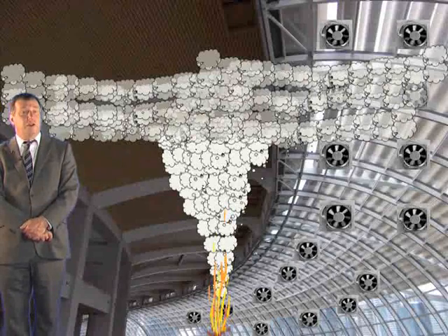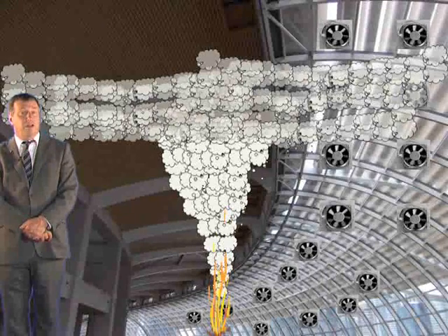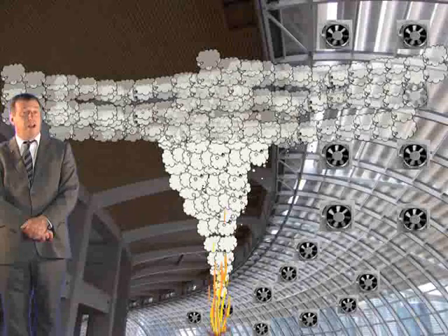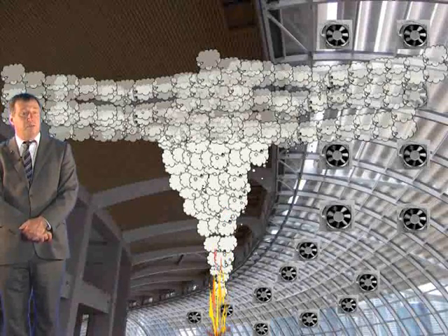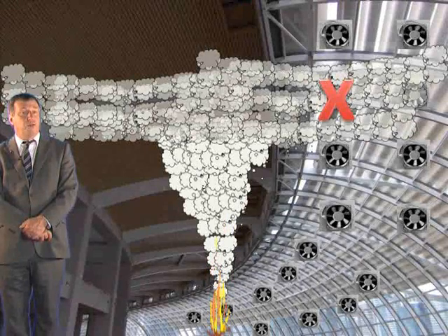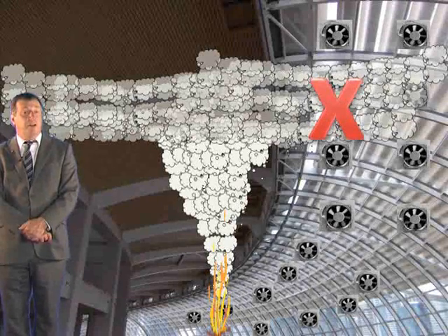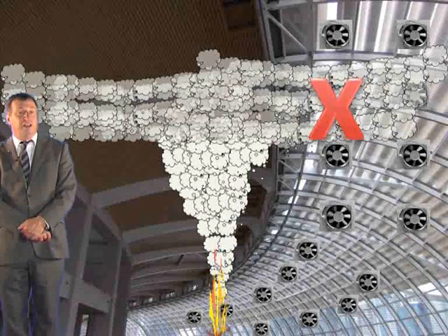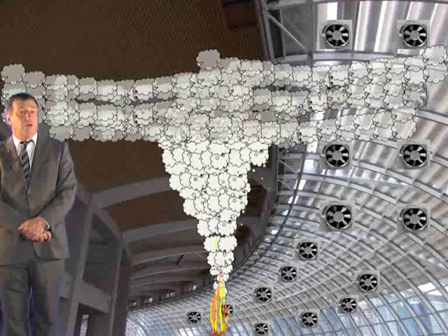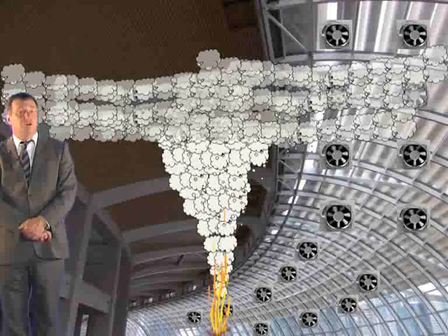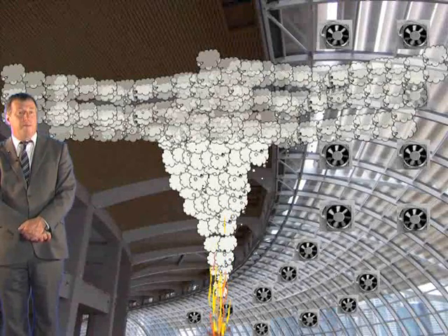If the effect has been ignored when calculating the necessary fan capacity or the necessary total area of natural ventilators, then it follows that plug holing at the design fire condition will represent a failure of the system, as ventilators will not be exhausting the full amount of smoky gases required. Some of their capacity will be used for extracting clean air. It follows that for efficient exhaust, the number of exhaust points must be chosen to ensure that no air is drawn up in this way.